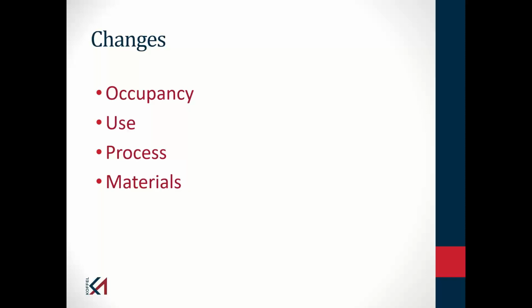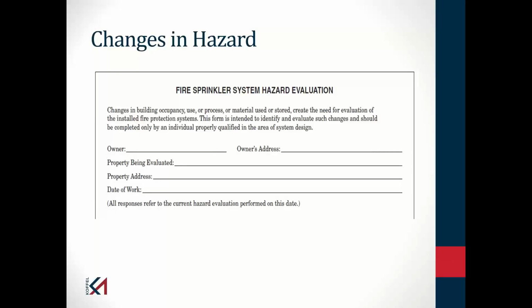You, the owner, are responsible for any changes that might affect the performance of the system, whether it's a construction change, a change in the way the space is being used, a change of occupancy classification, changing a process in a building, or changing the materials that are being used in that building. So just verify that somebody is doing that analysis for you. There is a form in the annex of NFPA 25. It's a pretty general form. It can help guide you through the hazard evaluation. Personally, I think there's a little bit more to it than what's on the form, but there is a form for that purpose.